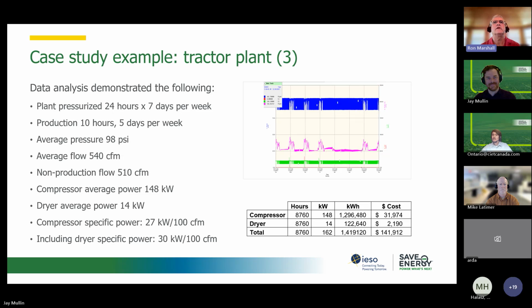So that made alarm bells ring in my head. I knew that I had discovered pretty significant leakage in the plant here. So it was a massive leaky plant that was leaking about 80% of the air that was being produced. Right. So we did specific power 27. It should be 18. And with the air dryer, it was a non-cycling air dryer, so inefficient, right? It's consuming the same power no matter what, even if the compressors are off, if that dryer remains on. So it makes the system less efficient. We were able to calculate the costs of the compressors and air dryers, come up with a total.